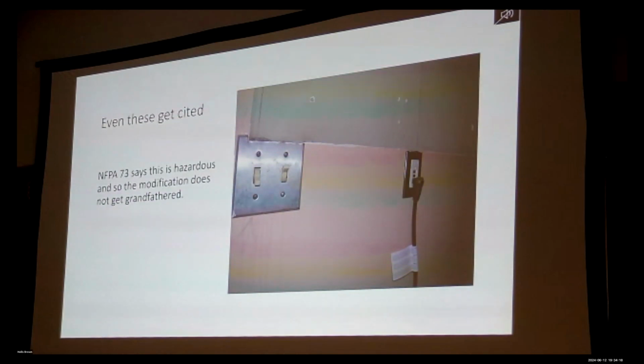This is also a violation. It's considered hazardous. Somebody wanted to put up a cabinet, or maybe a mirror, but probably a cabinet, and the cover plate was in the way, so they modified it. They trimmed it so it no longer meets the listing requirement for completing the enclosure safely, keeping the sparks in, keeping the bugs out, whatever.